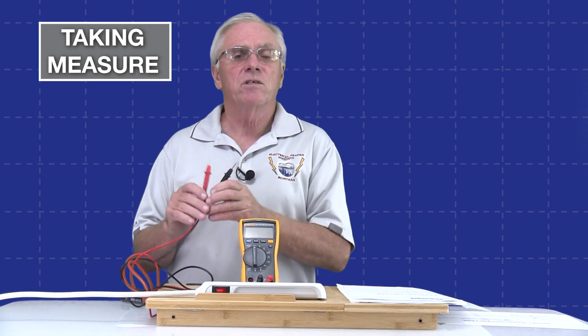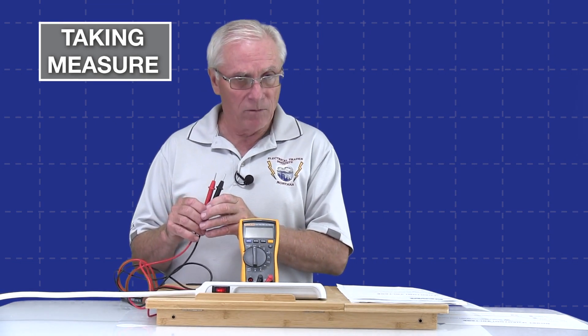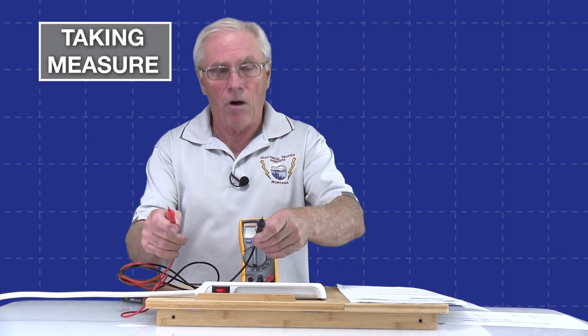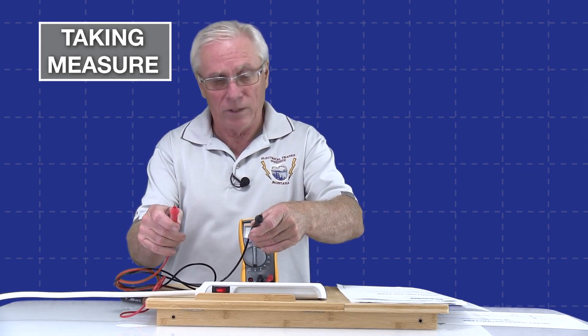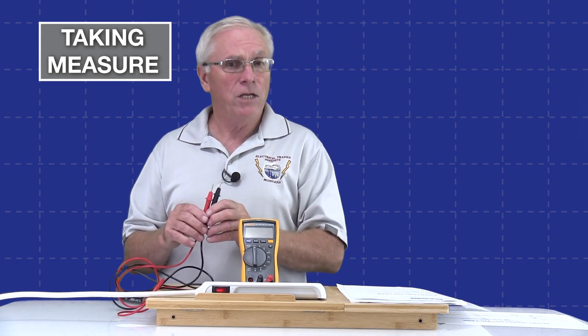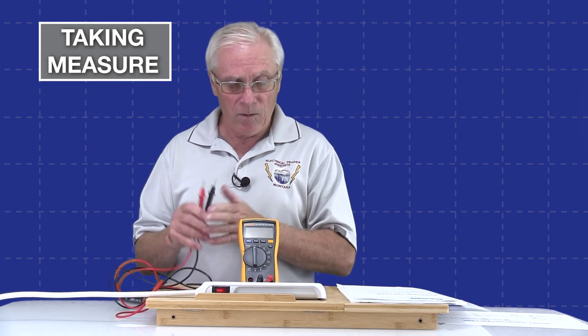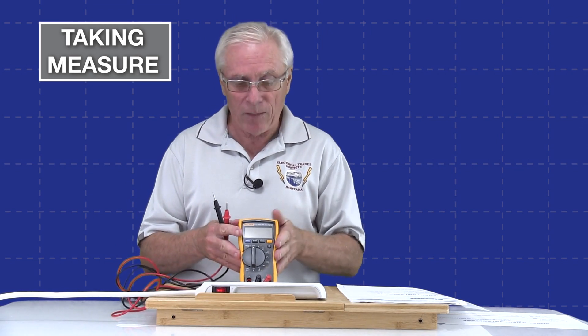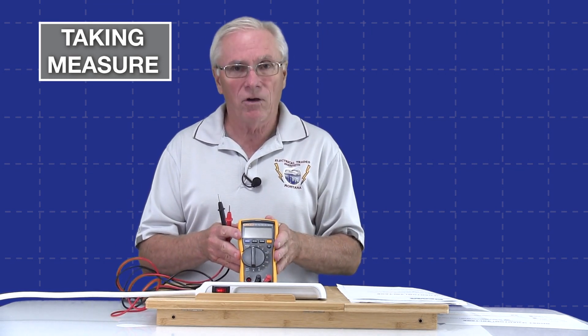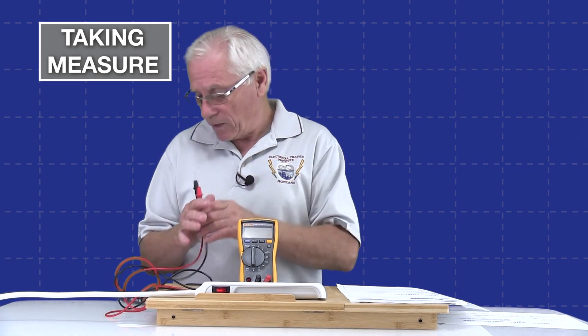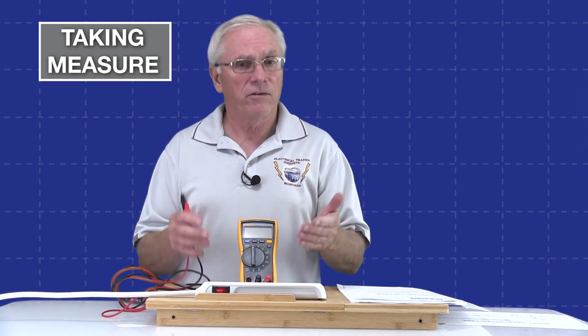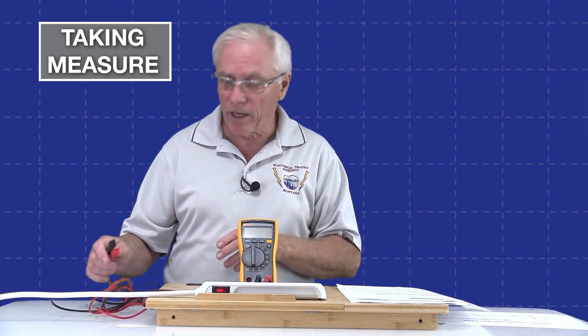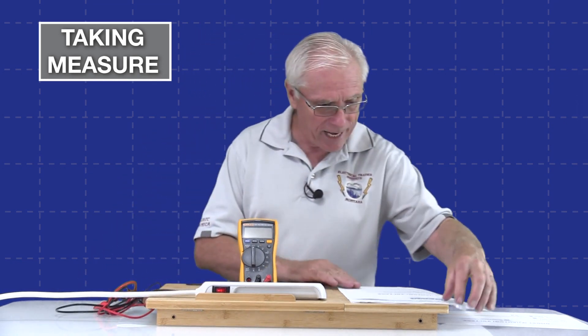When we talked in a previous video about meter loading, we discussed how when you take measure of a circuit, you're drawing voltage and also taking current into your meter and you can change the circuit and maybe impact the operation of a circuit. So they started developing meters with a high impedance input like this one. And in doing so, that also works with capacitive coupling to create the phenomenon of ghost voltage.